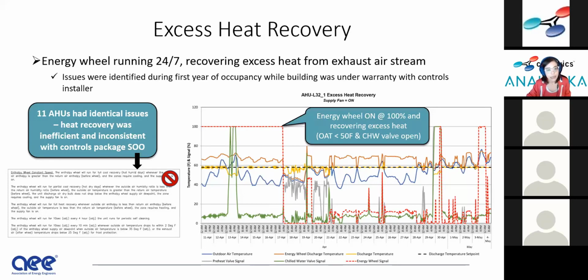Here's the time series chart, just the two points that are important. Most important, this red dotted line is the energy wheel signal, and this orange line, I need to point to it over here, is the energy wheel discharge temperature. What did we find? We found that the energy wheel was running 24/7, 100% speed, and we were recovering excess heat from the exhaust stream. So we need to modulate that energy wheel. We need to control that temperature to an optimum value.